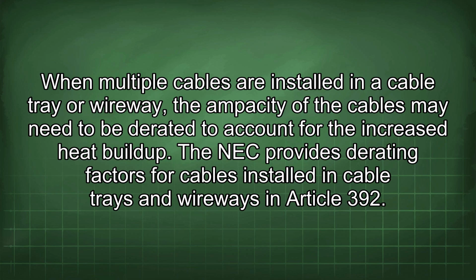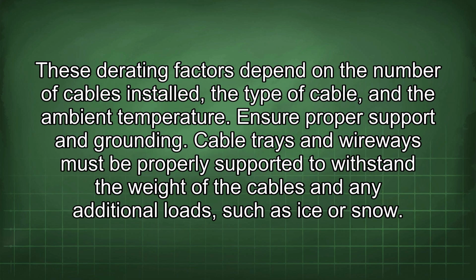Consider derating factors. When multiple cables are installed in a cable tray or wireway, the ampacity of the cables may need to be derated to account for the increased heat buildup. The NEC provides derating factors for cables installed in cable trays and wireways in Article 392. These derating factors depend on the number of cables installed, the type of cable, and the ambient temperature.